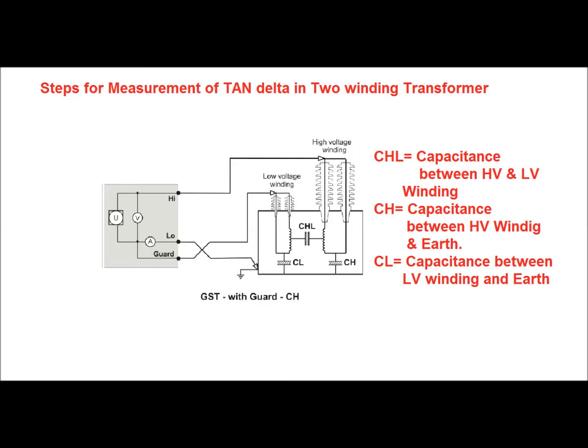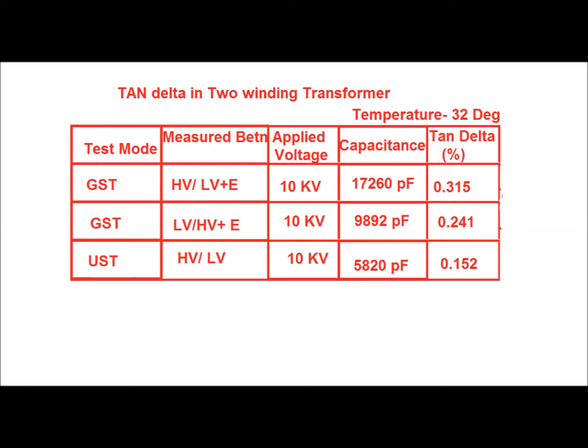The test results for the two-winding transformer capacitance and tan delta have been shown in this table. By GST mode, HV to earth capacitance value is 17,260 picofarads and tan delta is 0.315%. LV to earth is 9,892 picofarads and tan delta is 0.241%. Between HV to LV winding, the capacitance and tan delta are measured in UST mode. The applied voltage is 10 kV, the measured capacitance is 5,820 picofarads, and tan delta is 0.152%. Before measuring the tan delta test we have to record the voltage and temperature; here temperature is 32 degrees.